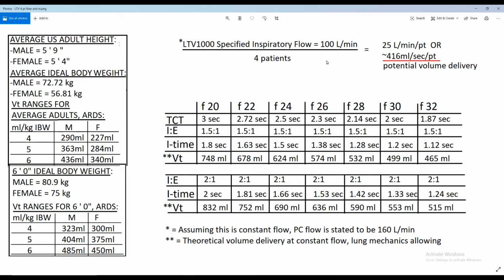So maybe it's able to put up with 100, or it's able to put out 160 liters per minute when it's in pressure control, but that would just be a peak flow, and then it would start decelerating. So to make the math easy and just figure out if this vent can come even close to giving us the volumes we want on a per patient basis, I used the 100 liters per minute of flow. So if it's 160, this would look even better. If it's actually 100, then this is the numbers we get. So moving on. 100 liters per minute, 416 mLs per second per patient.